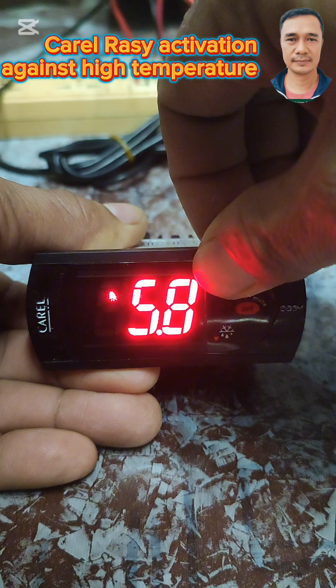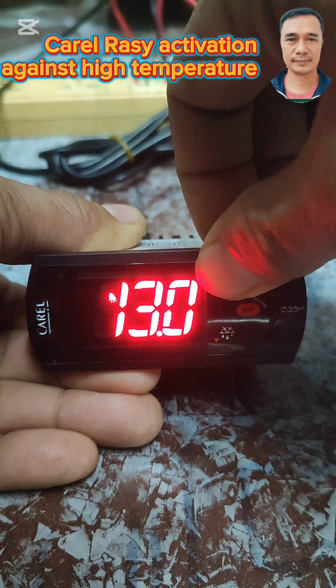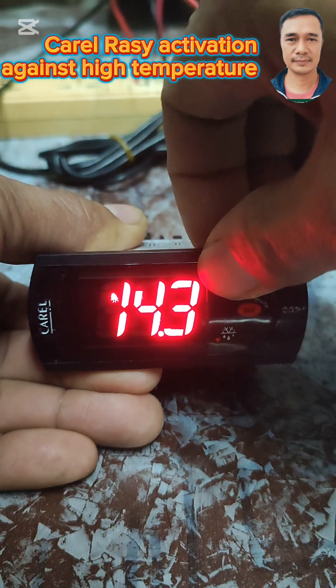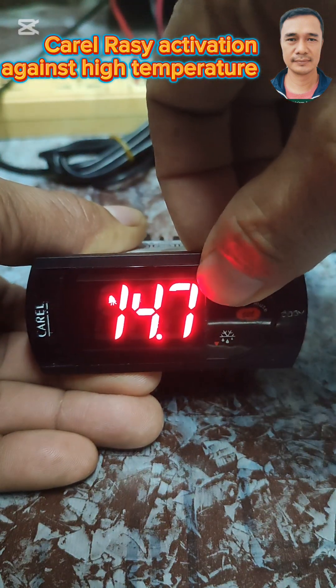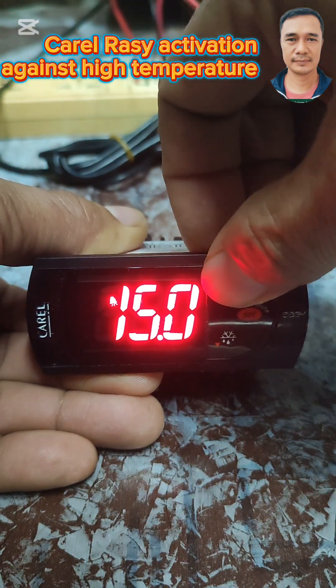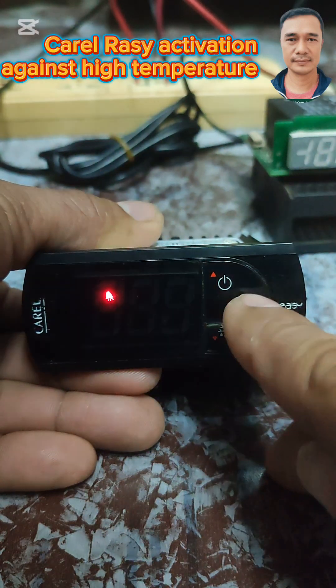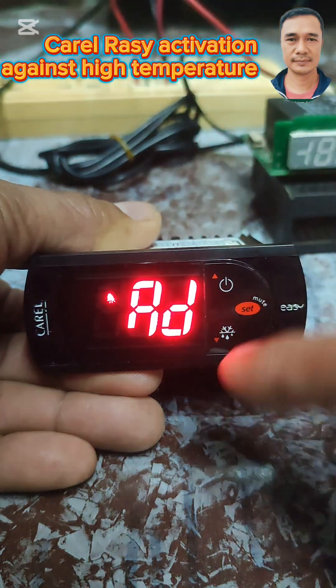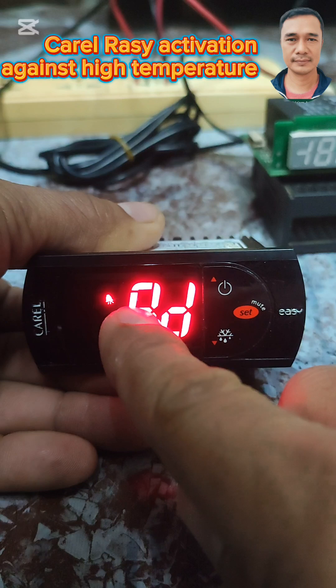It's up to you. Do not put something too low, otherwise it keeps triggering the high temperature alarm prematurely. You need to consider the defrost cycle and the frost time. Proceed to memorize.